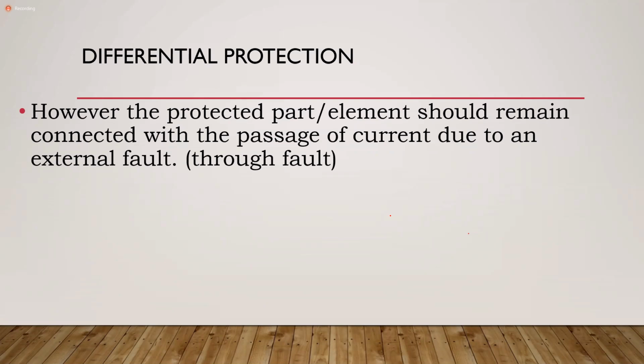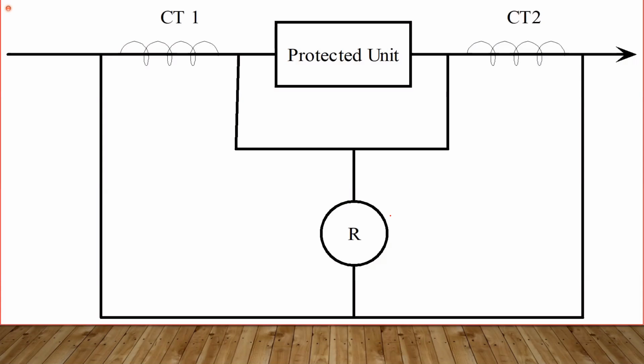So the fault that you created in the lab exercise was on the line. So what you will want to do is to remove the line, but in removing the line, you still want the transformer to remain. That is what we are talking about here. So you can allow the current to pass through to the fault, but if the problem is on the piece of equipment you are protecting, then you want to remove it. All right. That said, one way of achieving that is differential protection.